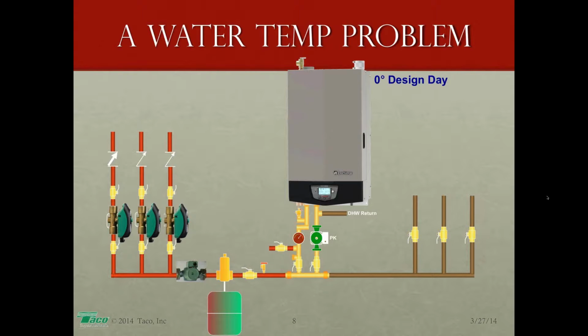What are the effects of an oversized boiler circulator? It's going to be really hard to maintain the delta T across the heat exchanger that you want, and that boiler's going to short cycle a lot, Tom. The more it short cycles, the more we wear stuff out. Overall, the less efficient and less economic that boiler is. So you don't want to oversize that circulator. Always do what they say to do.